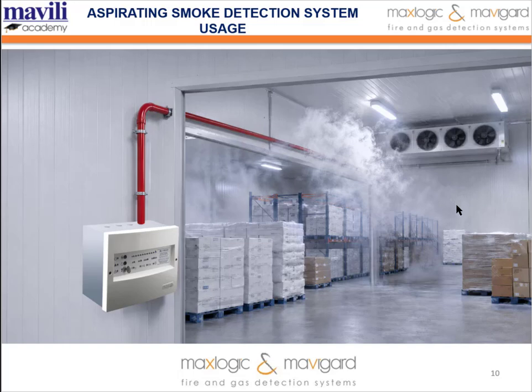So let's talk about the key benefits. So first of all, it reduces the risk of condensation and icing. Low temperature air from the cold storage facility can create condensation, as you know, when it reaches a warmer area or device inlet. So the heating unit reduces the risk, preventing the moisture or icing related problems in the pipeline and device inlet.